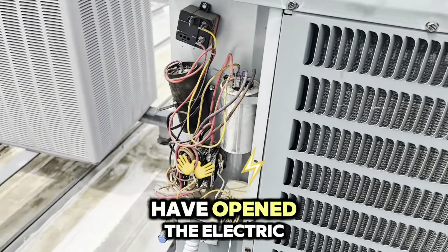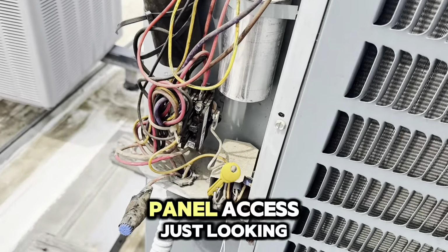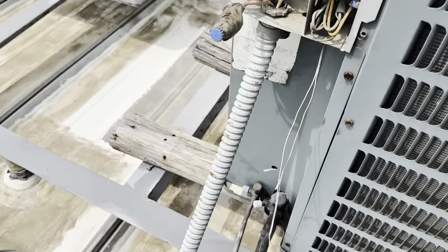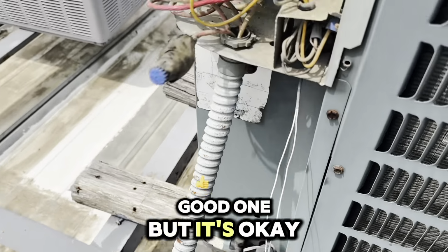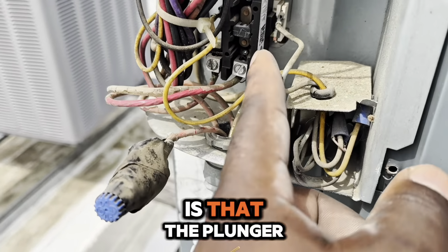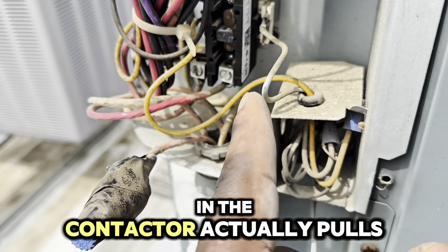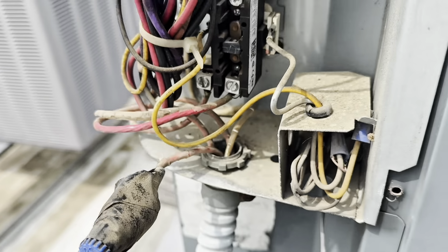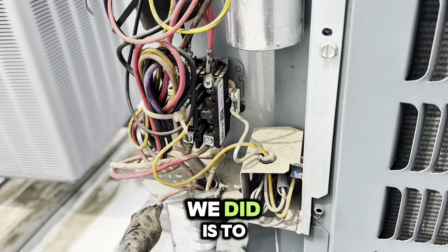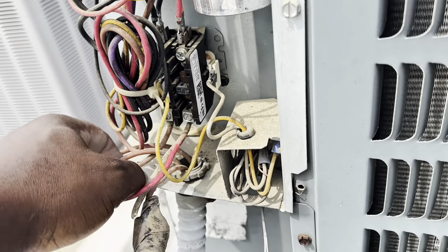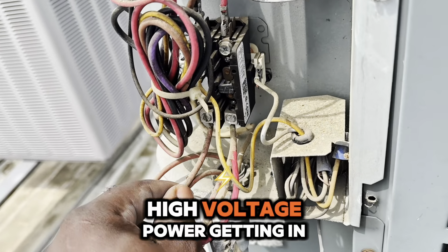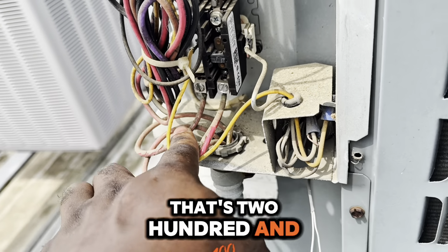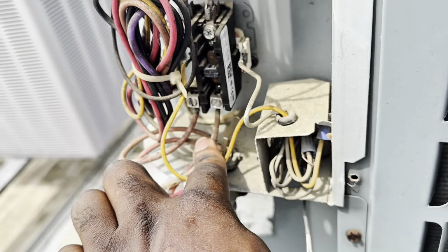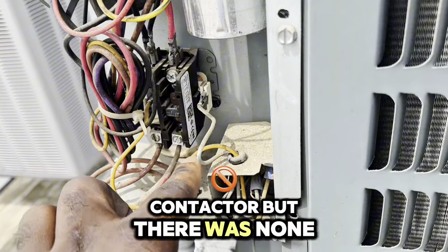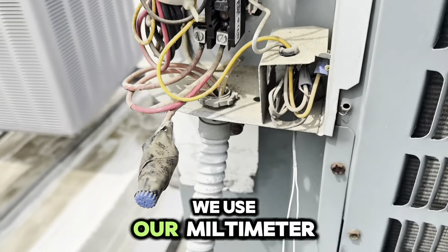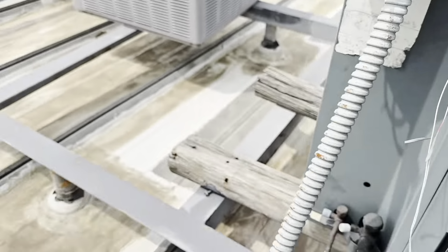So we have opened the electric panel access. Just looking at this is not a good one, but it's okay. What we have observed is that the plunger in the contactor actually pulls down, right? So the next thing we did is to verify if there is high voltage power getting in, that's 240 volt, getting into this contactor, but there was none. We used our multimeter, there's none.